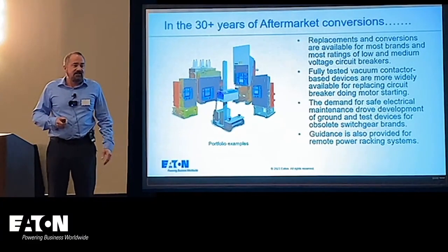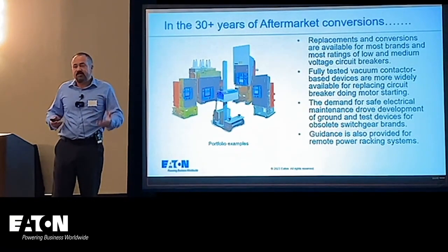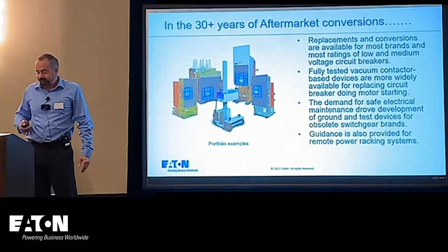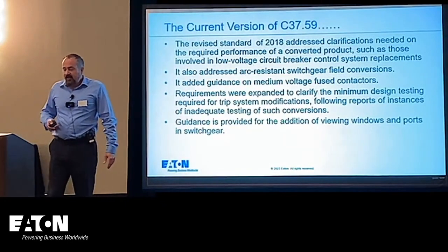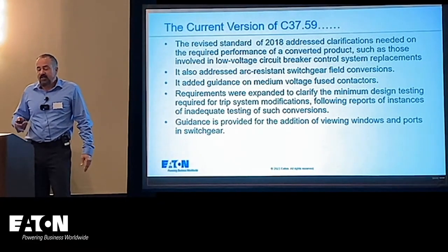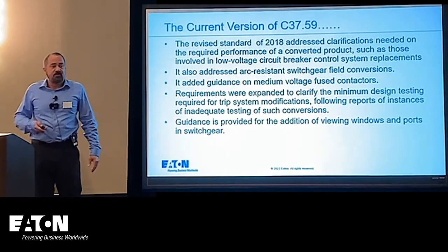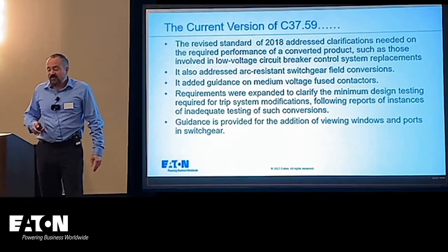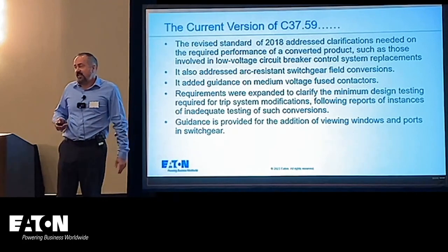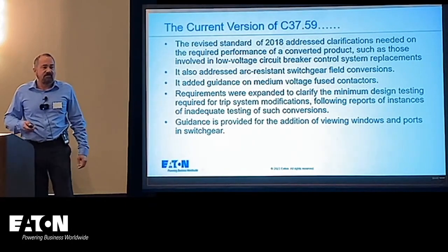In the 30 years since that standard came out, there have been a lot of different conversions and products by various manufacturers, and many recognized this as a big need in the industry. The 2018 version also addressed arc-resistant switchgear, added guidance on medium voltage fused contactors, and expanded requirements to talk about minimum design testing and guidance for adding viewing windows and ports in switchgear — which is very popular right now due to arc flash safety.